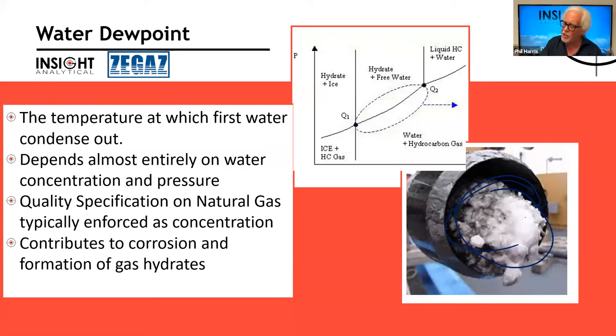It's an important quality specification on our natural gas. And we see it get enforced either as dew point or as water concentration. One of the important things to realize when we talk about the ZEGAZ device is it is an actual true measurement of the water dew point. And from that, we can calculate the water concentration. It is an actual dew point of the gas. Although it gets enforced sometimes as concentration, the really important thing to know in your processing facility is, where's my dew point temperature? Because that's when I risk making liquids and that's when I start to run into problems.